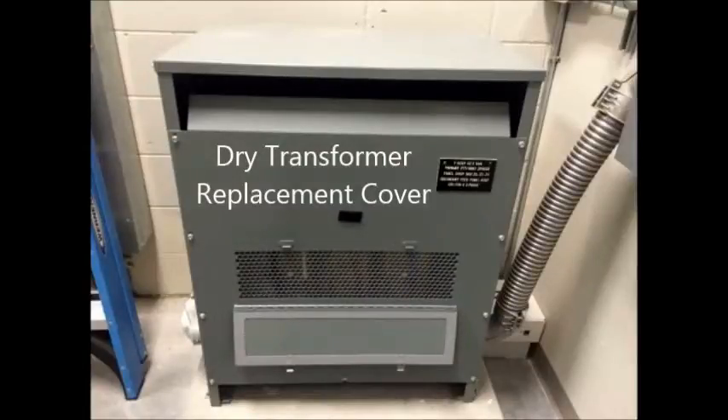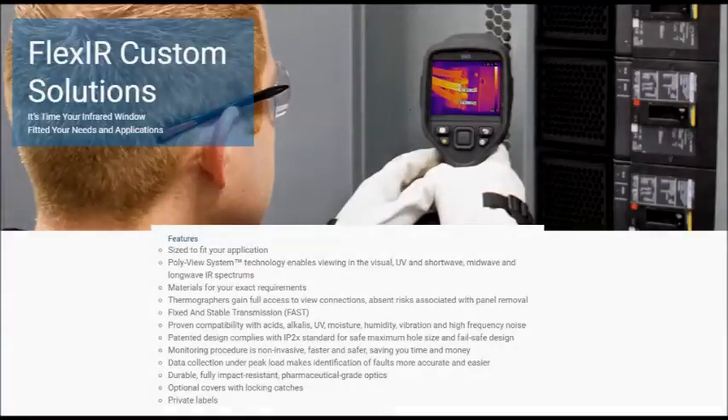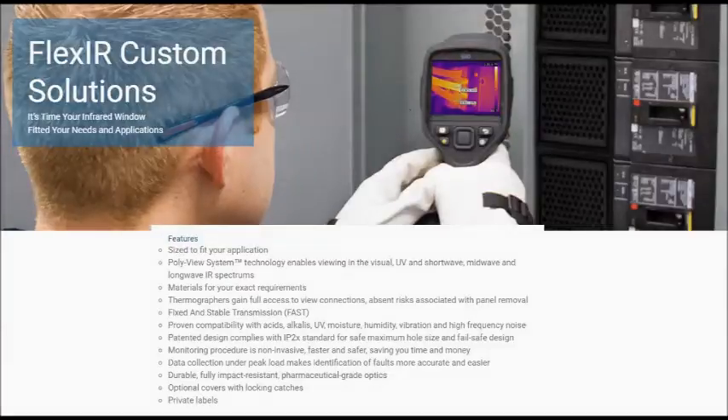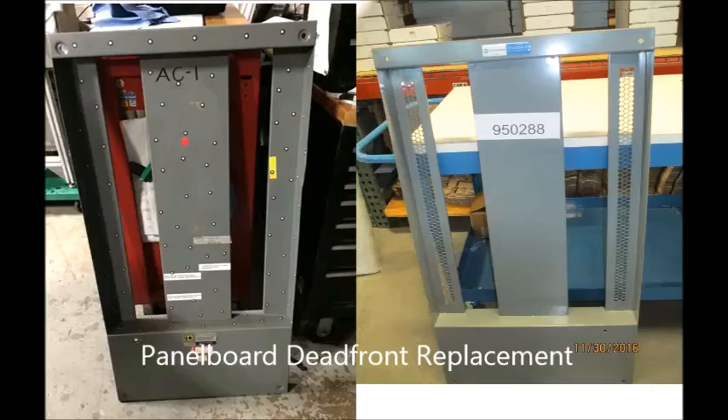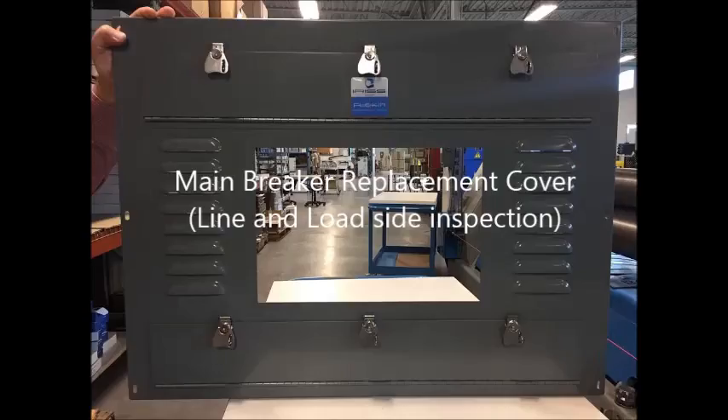IRISS FlexIR custom replacement panels and inspection windows provide two distinct advantages. First, they facilitate much faster field installation as no cutting, drilling and touch up painting is required. Many customers have very limited downtime for maintenance and custom replacement panels can be the only practical way to implement inspection windows. Second, many OEM designs make the retrofit of standard infrared windows impossible due to limited internal electrical clearances and structural interferences. Custom replacement panels can be designed to eliminate these problems and install in just minutes.